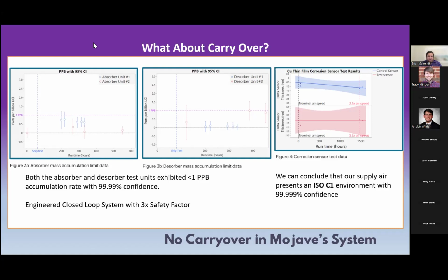As I mentioned in the very beginning of this presentation, liquid desiccant is not new. It's been on the industrial side for a long time. There have been other iterations of trying to use liquid desiccants in commercial applications. And sometimes design-wise, this has been met with some limitations and have led to some corrosive environments. And, again, making sure that this desiccant doesn't touch metal is the primary concern. Now, I will say over the next probably 5 years, we are going to see more manufacturers utilizing liquid desiccant. The number one factor that I would caution all of you on this call to pay attention to is what is the carryover? How good are you at keeping that liquid desiccant from touching metal? Because again, the moment it starts touching metal, you're going to have corrosive environment, and it's not going to go well for the system itself. We've been testing this for a long time. We are extremely confident, and we can prove the fact that we have effectively zero carryover.